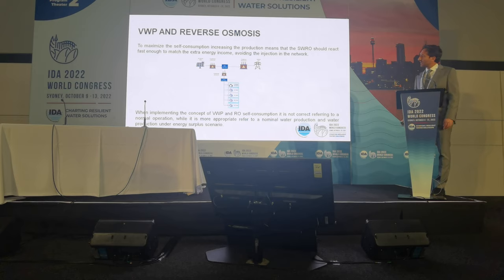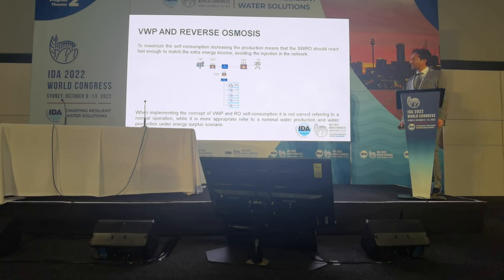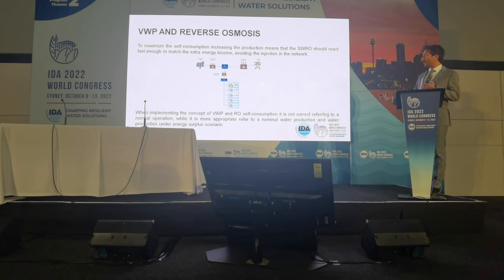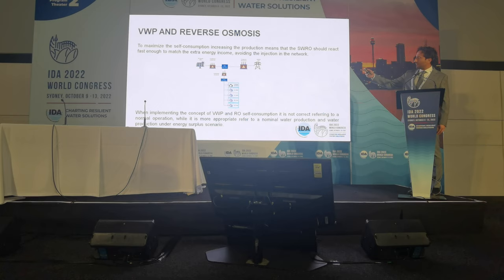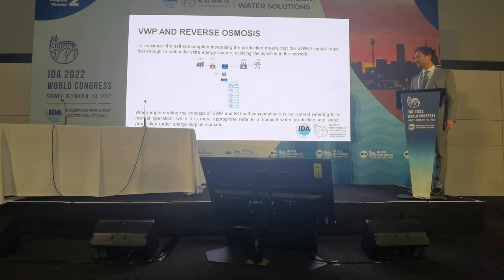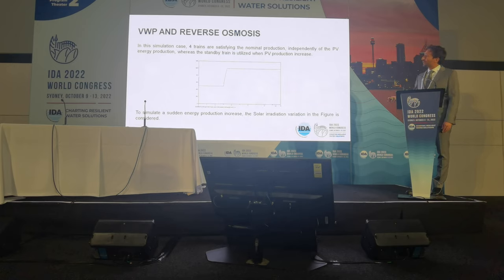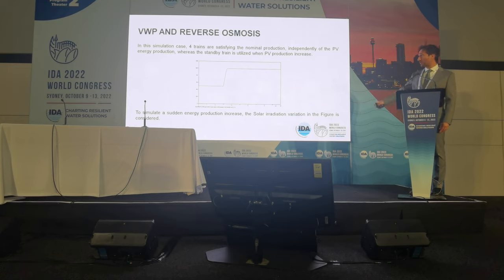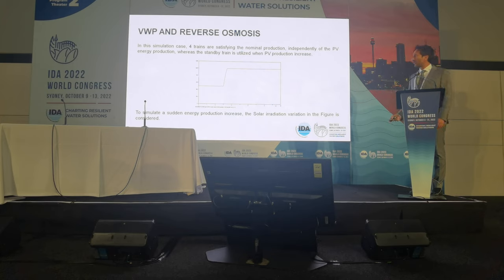This is a simulation we made, where a seawater RO plant has five trains with one on standby — though standby is not the proper term here, because the concept requires a nominal water production mode and a surplus-energy production mode. We have trains associated with HP pumps. If we increase production because irradiation jumps from 500 W/m² to 1,000 W/m² — for example, it was cloudy and now there is sun — we have a sudden production of energy from the PV.